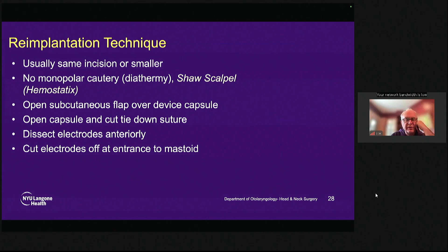My first cut is the electrodes as they enter the mastoid. In the old days, we thought we had to dissect out the ground wire, the full electrode, which you do not have to do. So we remove the receiver stimulator. We try not to squeeze it or traumatize it because we want to return it, with the electrodes we cut off, for cause of failure analysis.